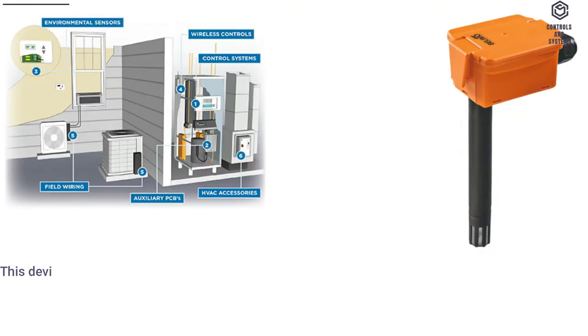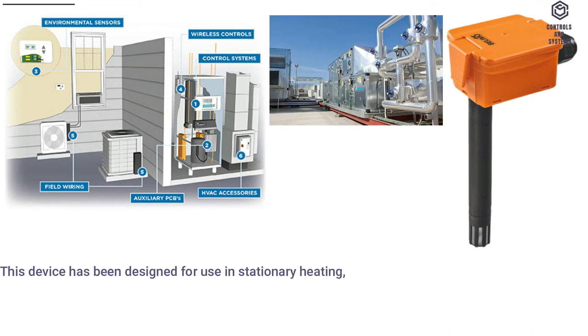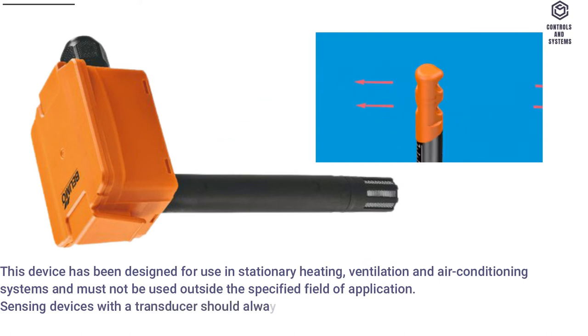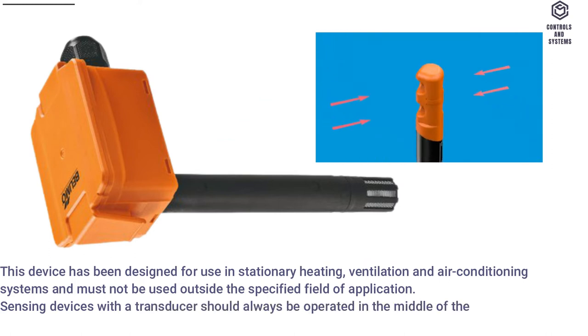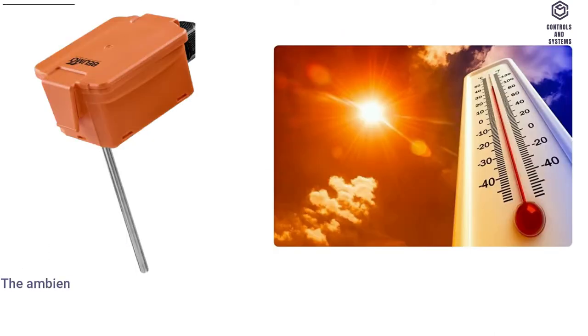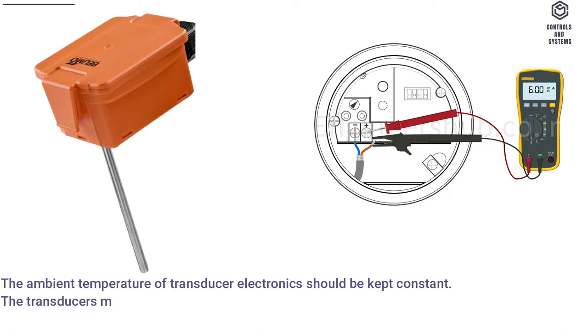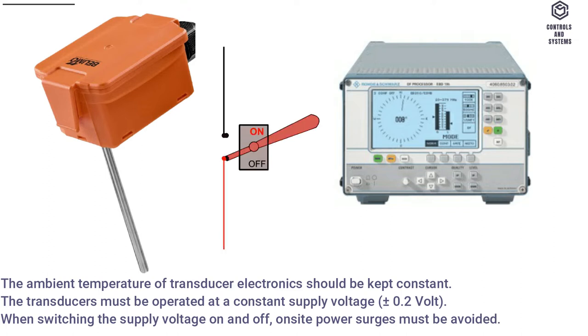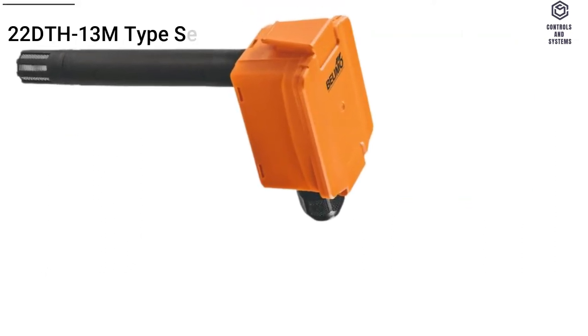Overview. This device has been designed for use in stationary heating, ventilation and air conditioning systems and must not be used outside the specified field of application. Sensing devices with a transducer should always be operated in the middle of the measuring range to avoid deviations at the measuring end points. The ambient temperature of transducer electronics should be kept constant. The transducers must be operated at a constant supply voltage of ±0.2 volt. When switching the supply voltage on and off, on-site power surges must be avoided.